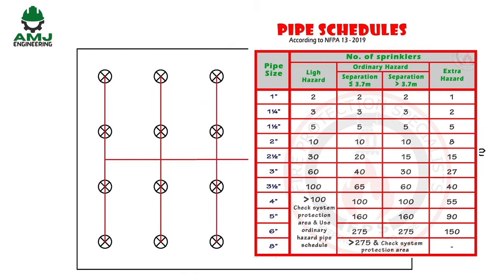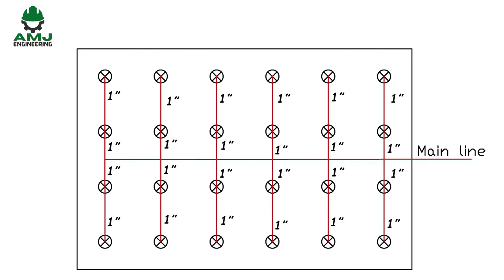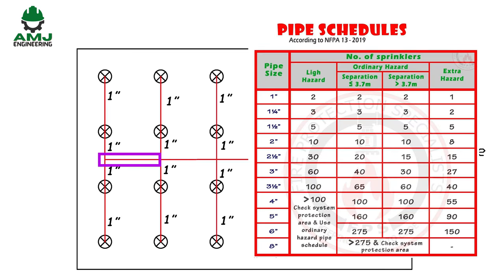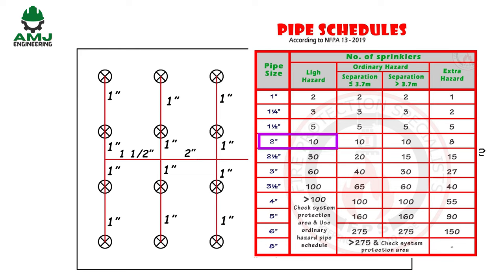Since our space is light hazard with no more than two sprinkler heads on each branch, the size of all branches is one inch. For the main line, always start from the end. The portion feeding four sprinkler heads should be one and a half inches. The portion feeding eight sprinkler heads should be two inches. All the rest are two and a half inches because the number of sprinkler heads is more than 10 and less than 30.